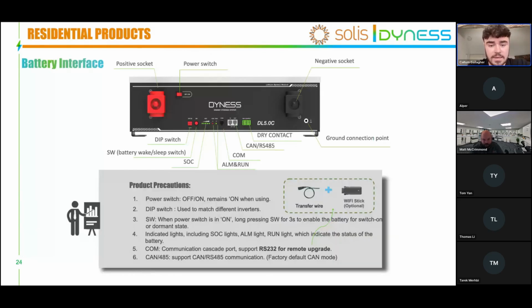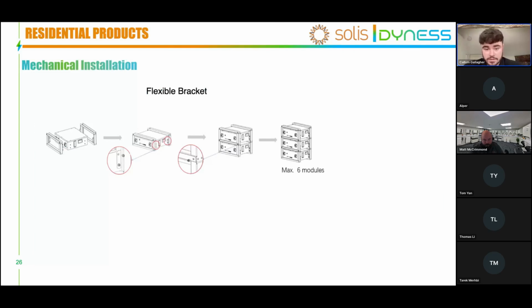So this is how it looks on top there. You've got your positive and negative sockets, your CAN ports, and your dip switch, and then you've got indicators for the state of charge, alarms, and the soft wake button as well. You can install these in a rack system. We've seen it installed the majority of the time wall mounted or floor mounted, but you can install these in a rack system. If you need a rack system for any jobs, just let us know and we can help source them. We don't provide it, but we can source them for you.